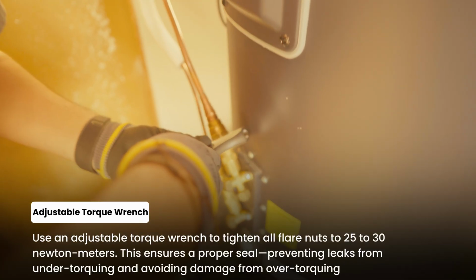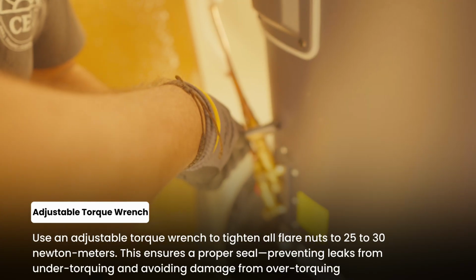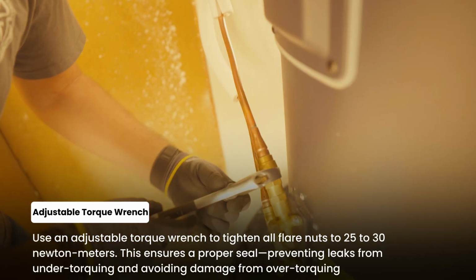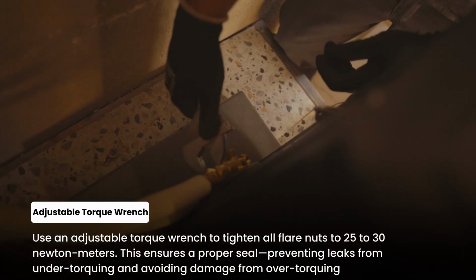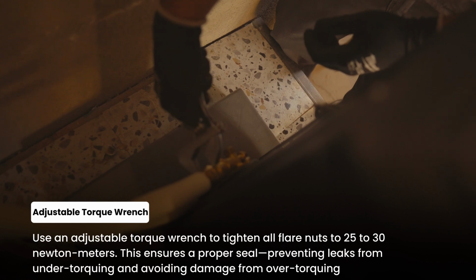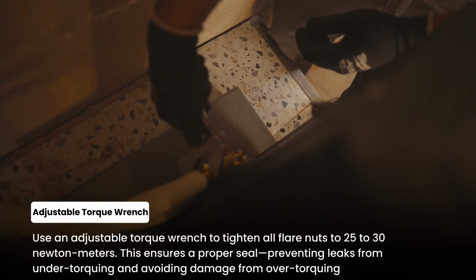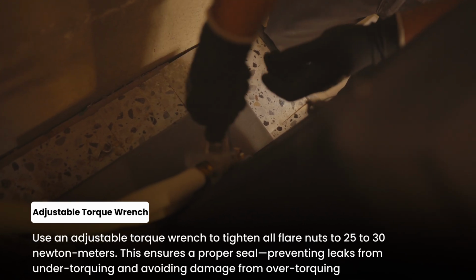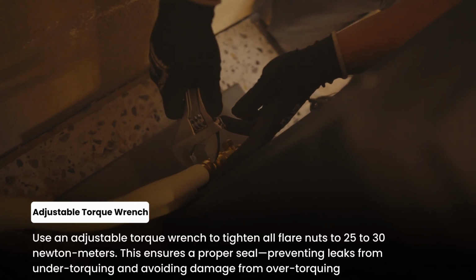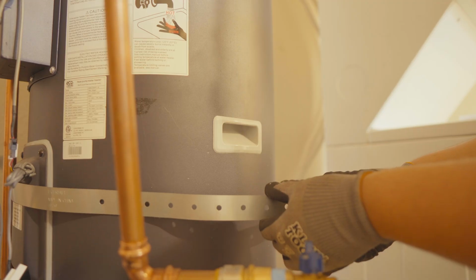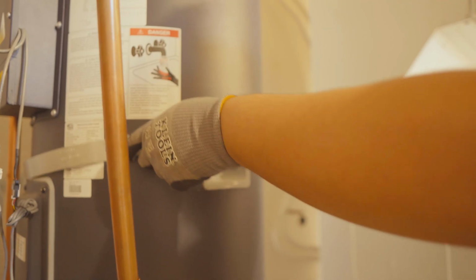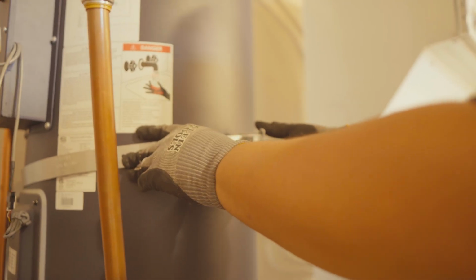Use an adjustable torque wrench to tighten all flare nuts to 25 to 30 Newton meters. This ensures a proper seal, preventing leaks from under-torquing and avoiding damage from over-torquing. Once everything is torqued correctly, the refrigerant lines are fully installed. Be sure to install earthquake or safety straps according to your area codes.